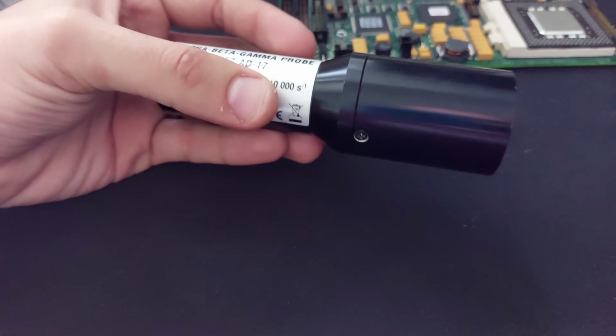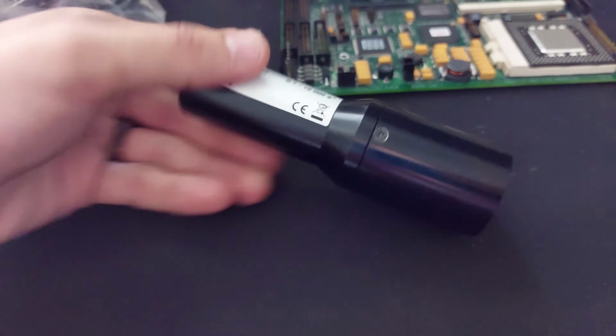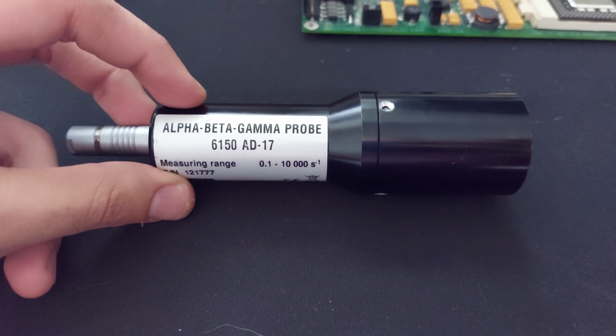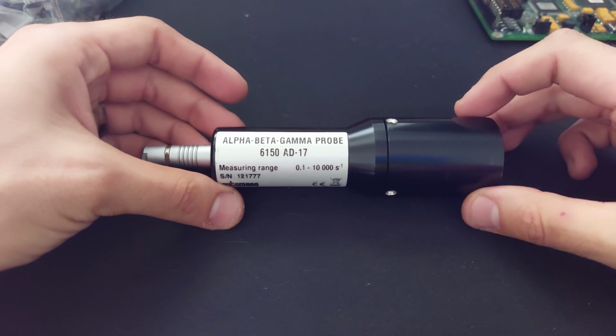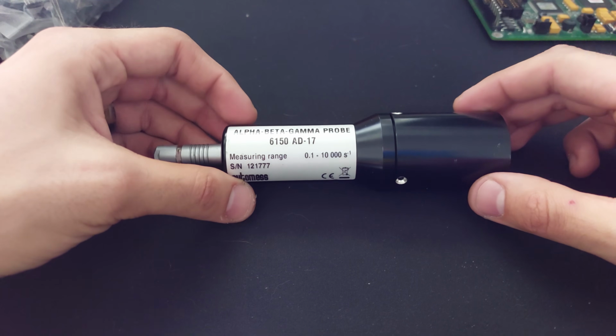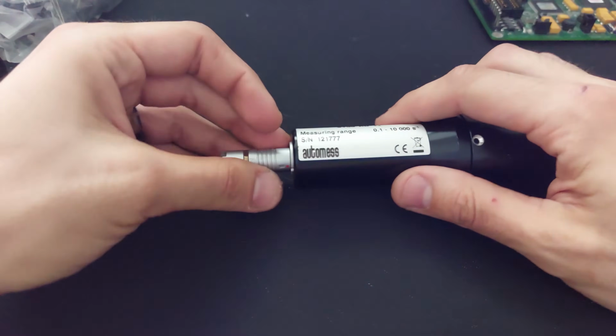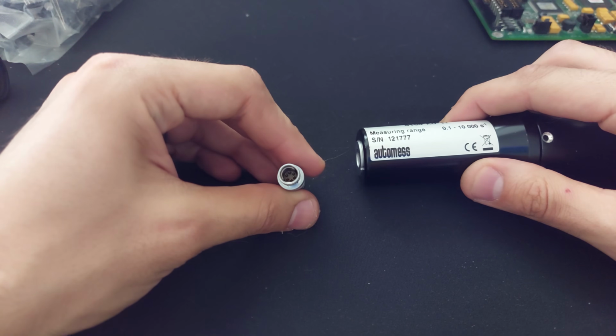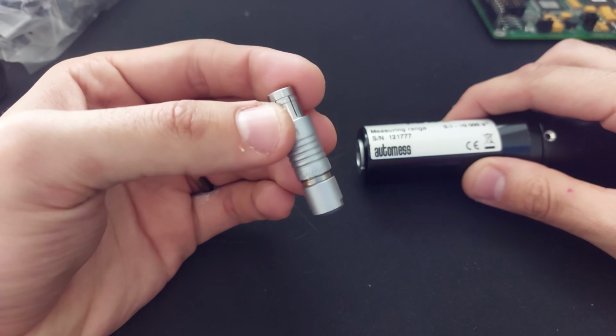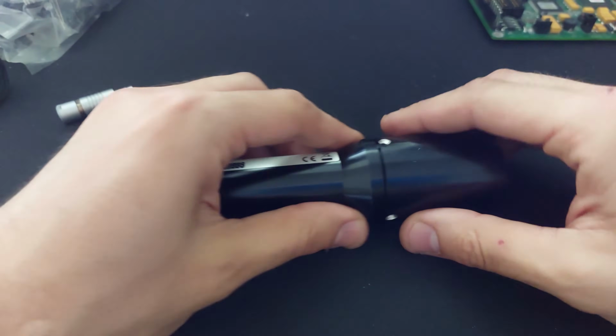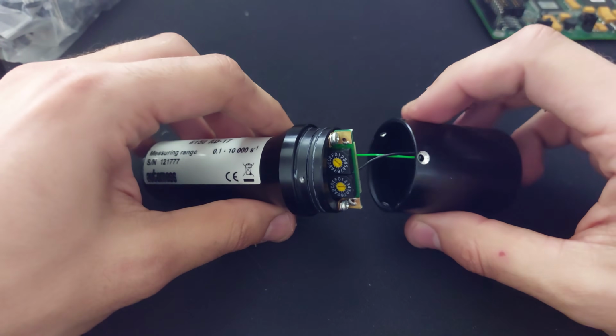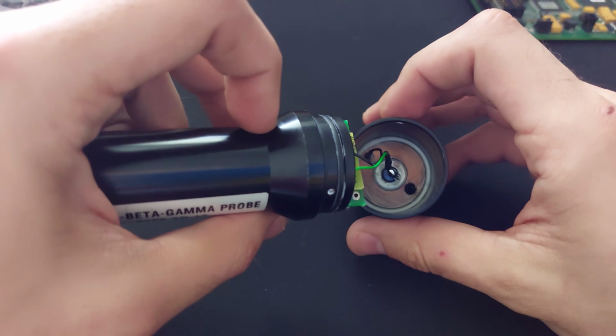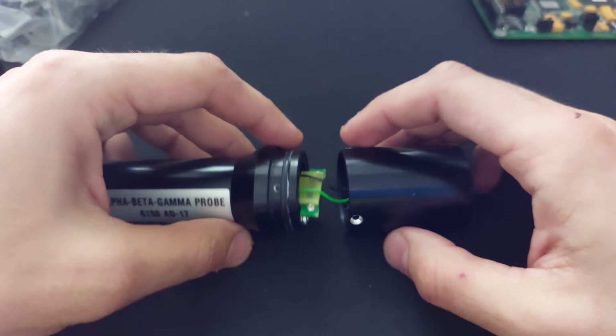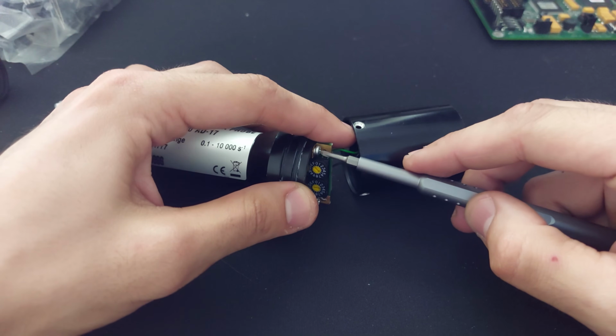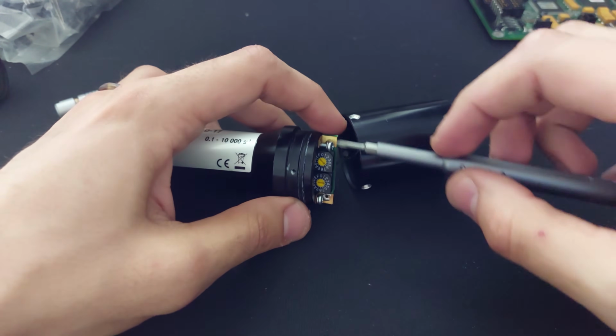I'm suspecting this is a built-in high voltage generator probe, so it doesn't require an external high voltage supply from the base unit. And after we take out some screws, I'm expecting also a weatherproof seal of some description. So let's take out the connector. You can see it's a 6-pin plug, very nicely made, very expensive. Actually, extremely expensive. These are rated for thousands of mating cycles, and they're very, very nice. So we can see a PCB with a couple of switches and the Geiger tube itself in the end. And the thing caked in a bit of white grease is an O-ring, so the whole thing is basically waterproof.